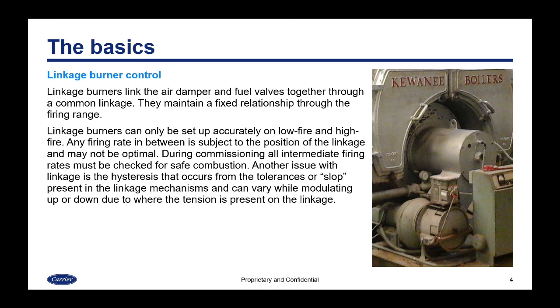Another issue with linkage is that the hysteresis occurs from the tolerance or the slop present in the linkage mechanism, meaning that traveling up or down in the firing rate, you may not be in the same exact position. And this can vary while modulating up and down due to where the tension is present on the linkage at any given time.